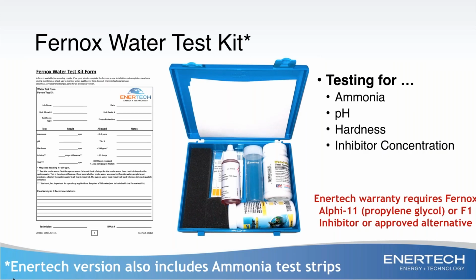One of the really important parts of the installation and long-term reliability is making sure that we have good water quality. This is really, really crucial in our air to water products, but also our geothermal products. And we actually offer Fernox as our preferred antifreeze and inhibitor. So along with those chemicals, we offer this test kit. It's a pretty simple kit, really. The original test kit had a lot more tests in it, but as we narrowed it down to what really is causing the most problems with regard to heat exchanger issues, pump failures, those kind of things, it really boils down to primarily pH and hardness.